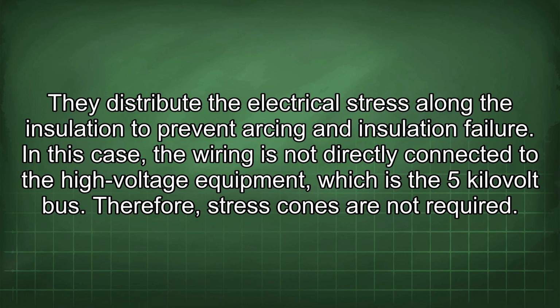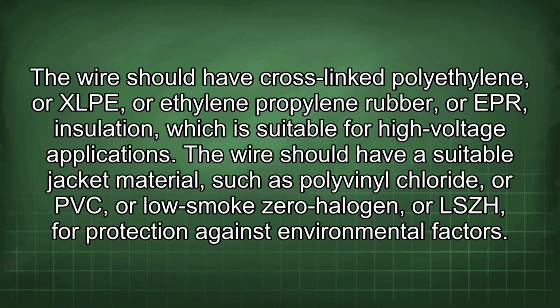In this case, the wiring is not directly connected to the high voltage equipment, which is the 5 kV bus. Therefore, stress cones are not required. The wire should have cross-linked polyethylene, or XLPE, or ethylene propylene rubber, or EPR, insulation, which is suitable for high voltage applications. The wire should have a suitable jacket material such as polyvinyl chloride, or PVC, or low smoke zero halogen, or LSZH, for protection against environmental factors.